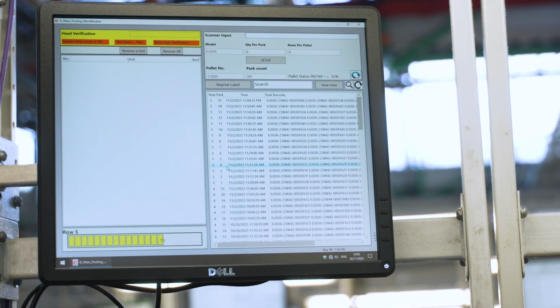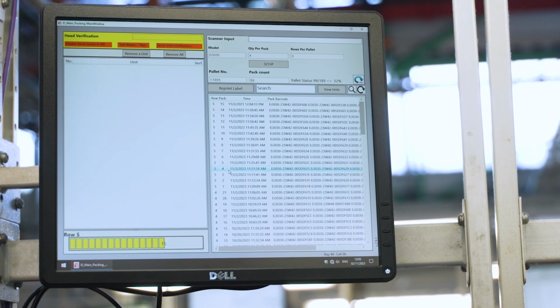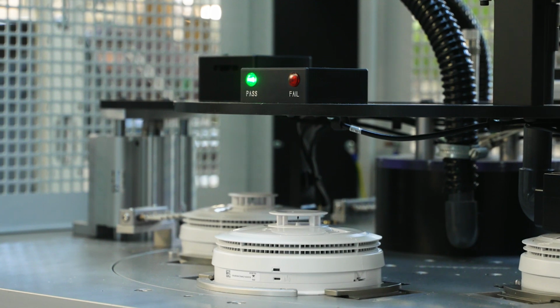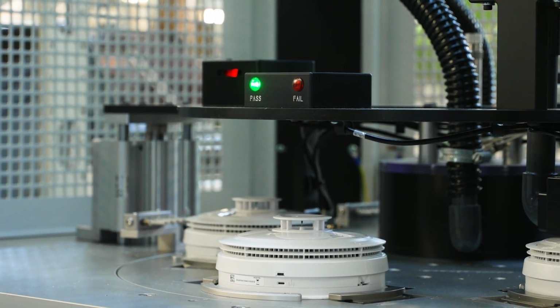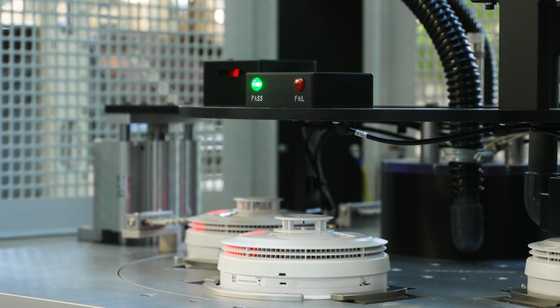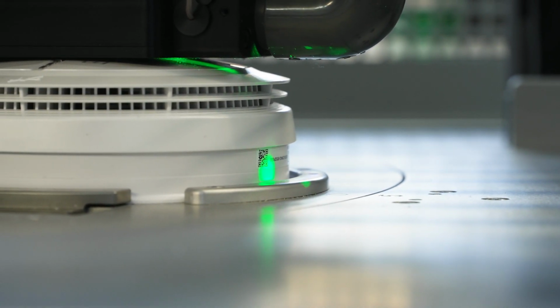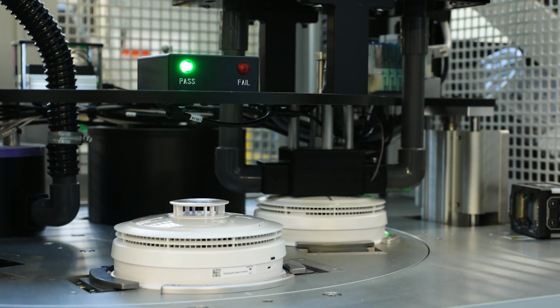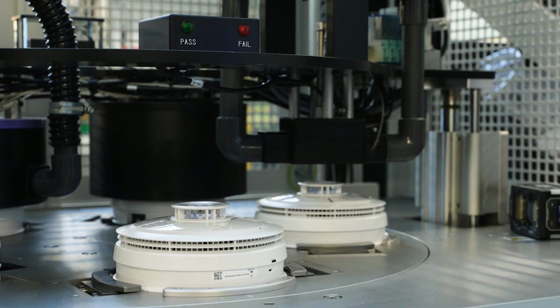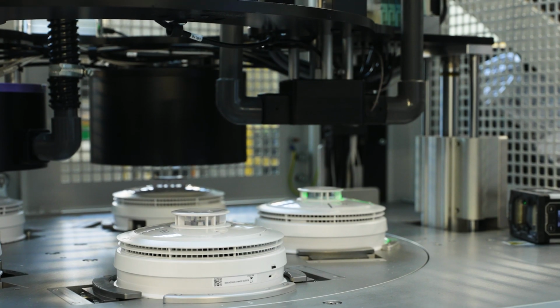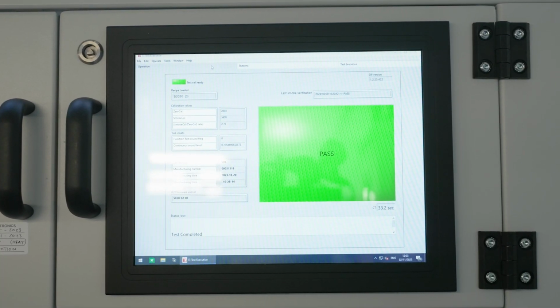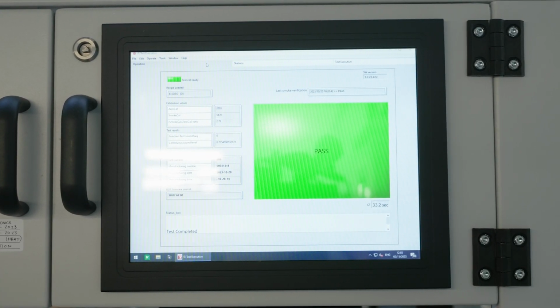Like all other test stations, we will query the device's serial number. It goes into 2 stages for smoke calibration. The first stage, it goes into what we call a zero smoke calibration state, and it creates a zero smoke environment. We can then instruct the device that when it's measuring this level, it's considered a no smoke environment. It moves to a smoke calibration chamber, where we inject a known quantity of smoke into the device. We can then instruct the device that this is the level of smoke that you need to trigger at.